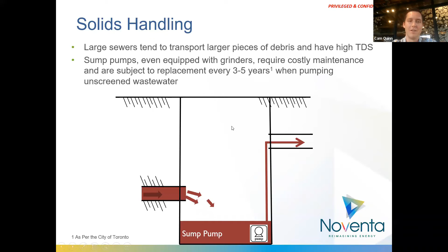Pumping sewage is not a desirable service, both for maintenance and for selecting equipment, because large sewers tend to transport large pieces of debris and have high TDS, or total dissolved solids. There are some pictures courtesy of Toronto Water here. Sump pumps, even if equipped with grinders, require costly maintenance and are subject to replacement every 3 to 5 years when pumping unscreened wastewater. This is a big issue you need to put thought into overcoming, and I'll show how we've overcome it in a couple slides.